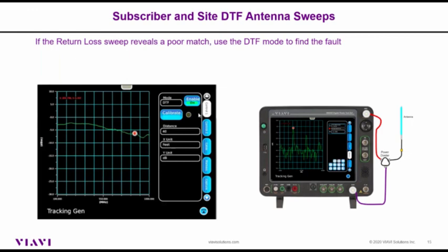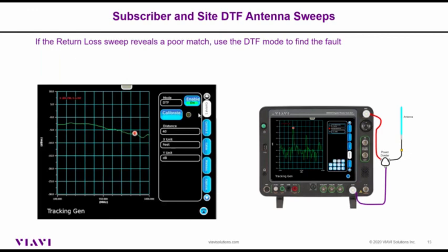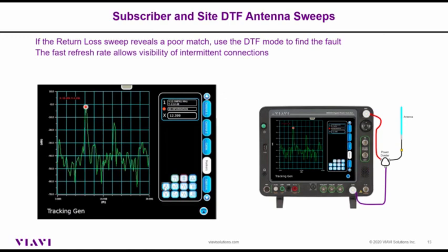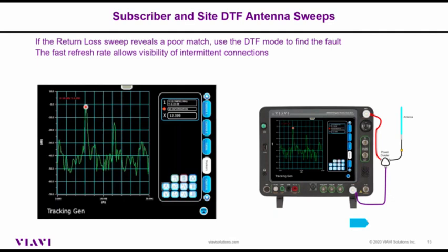You can switch the display from return loss to VSWR and change the scale factor — for example, from 2 to 1 — to magnify the trace and see that this particular antenna is tuned to the higher-frequency 800 band. It will reflect lower-frequency signals back to the transmitter. If the return loss sweep reveals an issue, you can do a distance-to-fault sweep using the power divider. The distance-to-fault plot has a very fast refresh rate of about two seconds per sweep, so if things are changing — like the wind blowing the antenna — you would see movement on the plot.